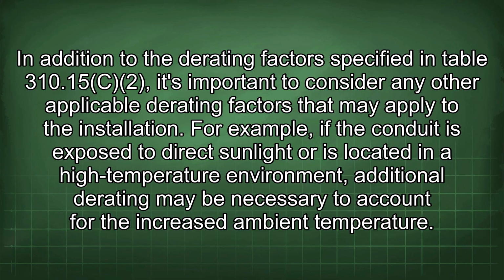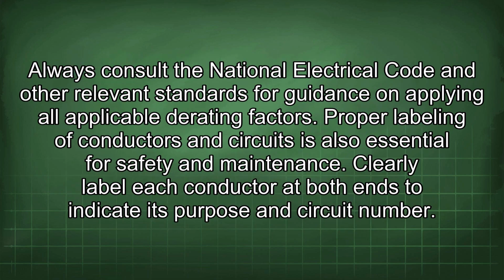For example, if the conduit is exposed to direct sunlight or is located in a high-temperature environment, additional derating may be necessary to account for the increased ambient temperature. Always consult the National Electrical Code and other relevant standards for guidance on applying all applicable derating factors. Proper labeling of conductors and circuits is also essential for safety and maintenance.